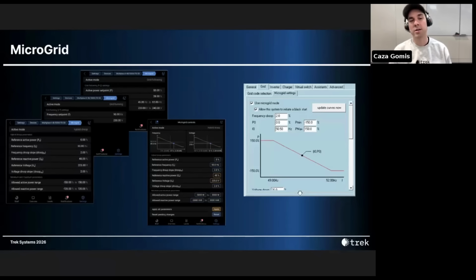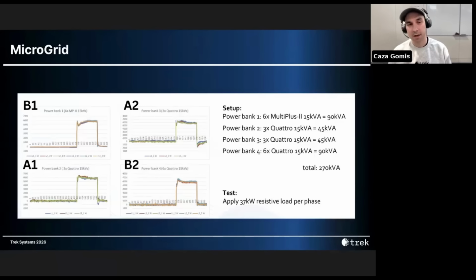What really makes this possible is a feature called hybrid droop mode, which adjusts power output based on frequency and voltage deviations. For example, as a load increases, the frequency drops and the inverter increases its power output accordingly. So each inverter can respond independently to the grid conditions, allowing them to share loads proportionally based on the droop characteristics. This is a test published by Victron that shows all of this in action.